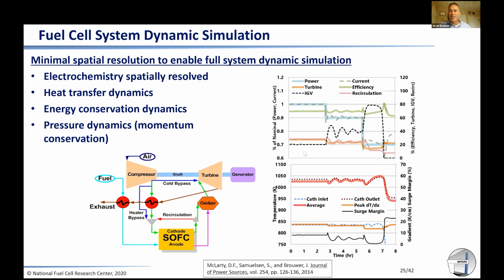There's a lot of things we were doing in this particular control strategy. We were manipulating inlet guide vanes that you see here in the checked black line. You can see we were able to keep the efficiency pretty high over all the dynamic changes, and the power was changed from 100% full power to 90%, down to 70% full power, with all the temperatures managed well throughout the system.